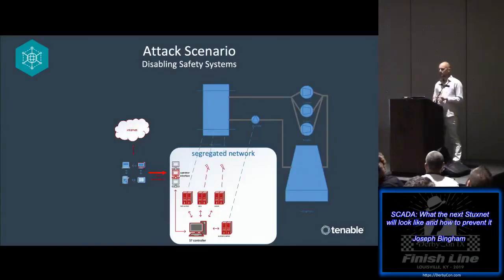The last part of the attack is to disable the critical and redundant manual and automatic safety measures, those safety systems we looked at in the schematic. The attacking malware can replace the logic in the emergency core coolant system and in the SCRAM control rod insertion so they won't trigger from automatic or operator manual controls. This allows the core time to heat beyond design limits and start either a meltdown process or an internal steam explosion, pushing conditions beyond design specifications.